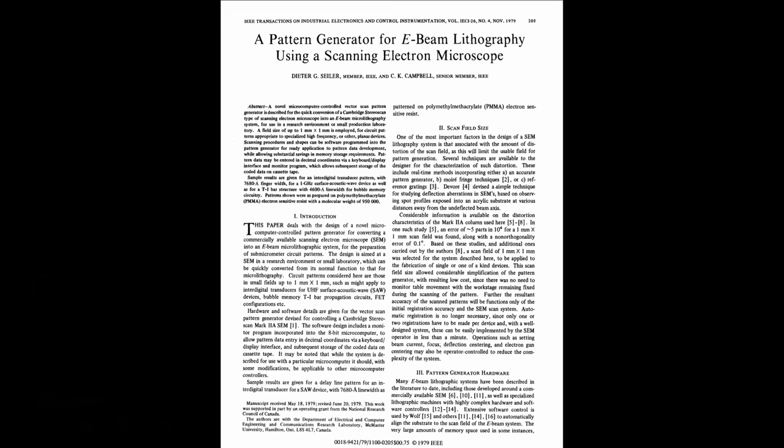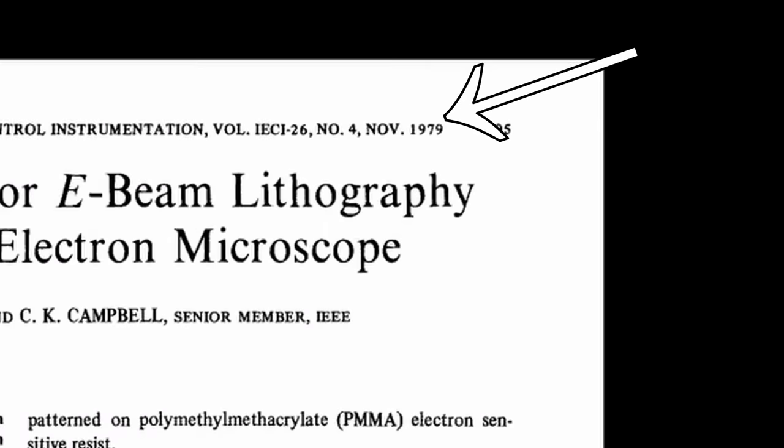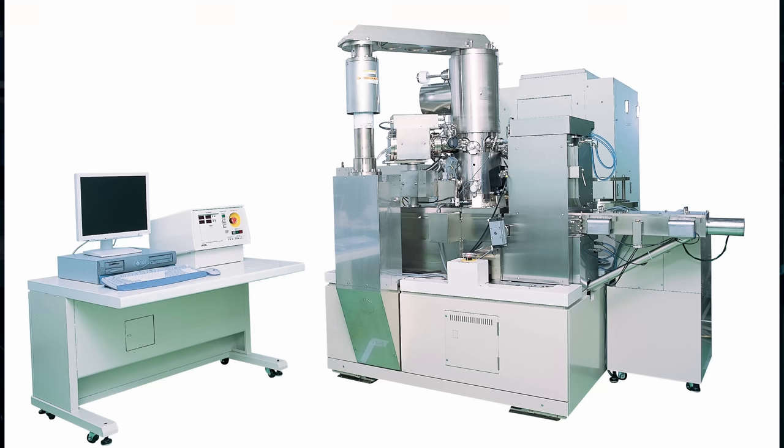I'm using my scanning electron microscope as an improvised electron beam lithography machine — a time-honored tradition. SEMs have been converted into litho machines for basically as long as SEMs have been around. There are some downsides to using an SEM this way, and it's not ideal, although it does get the job done. If you're at a professional institute, you'll probably have a dedicated EBL machine, which offers much better control of the electron beam, higher accelerating voltages, and much better patterns a lot faster.